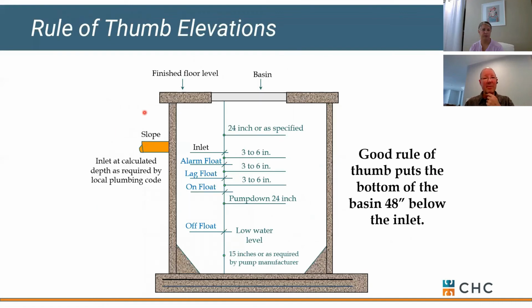The other thing we need to keep in mind is that we need room in here to not only maintain some minimum water level to cool our pump or our motor, more importantly, but also some usable water so our pump doesn't short cycle, and then room to turn on our standby pump if needed, and also to sound a high water alarm, all that without backing water up into our invert.